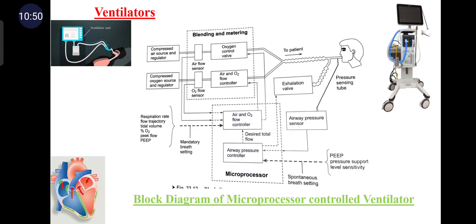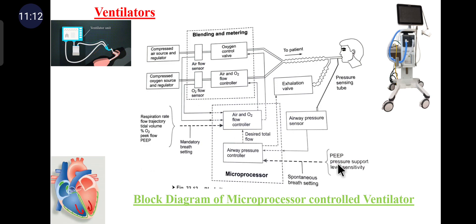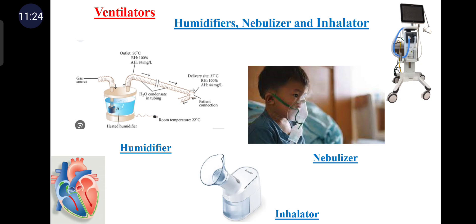The electronic control system uses one or more microprocessors and software to perform monitoring and control functions. Parameters include respiration rate, flow waveform, tidal volume, oxygen concentration of the delivered breath, peak flow, and PEEP. The PEEP selected in the mandatory mode is used only for control of exhalation flow. The microprocessor utilizes these parameters to compute the desired inspiratory flow trajectory, and the overall system includes monitors for pressure, flow, and oxygen fractions.